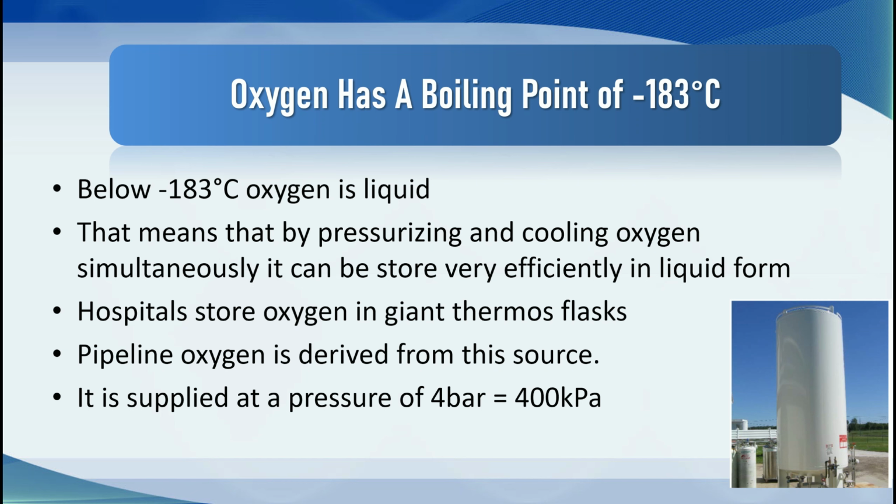If you're working in the operating room, there is a button on your anesthetic machine called oxygen flush. If you push this button, oxygen gets flushed at 4 bar. This is not the safest thing that you can do to your patient.